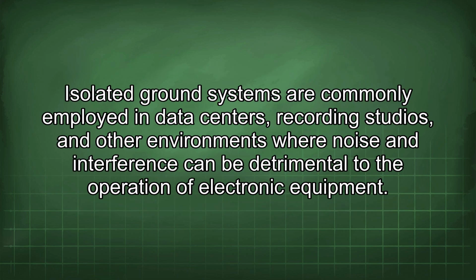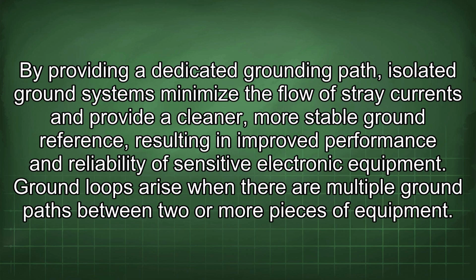Isolated ground systems are commonly employed in data centers, recording studios, and other environments where noise and interference can be detrimental to the operation of electronic equipment. By providing a dedicated grounding path, isolated ground systems minimize the flow of stray currents and provide a cleaner, more stable ground reference, resulting in improved performance and reliability of sensitive electronic equipment.